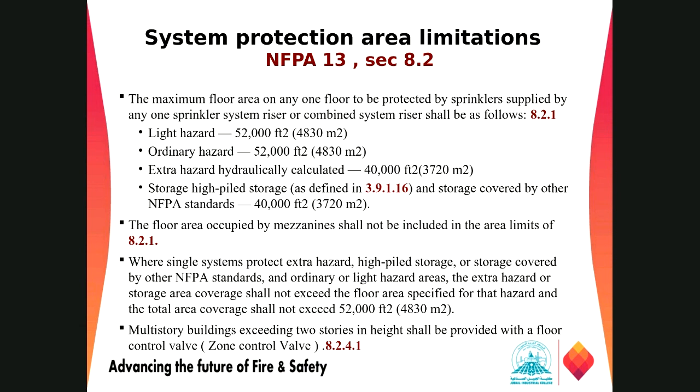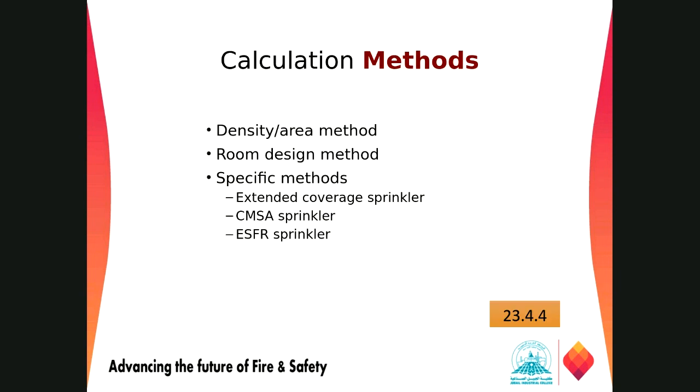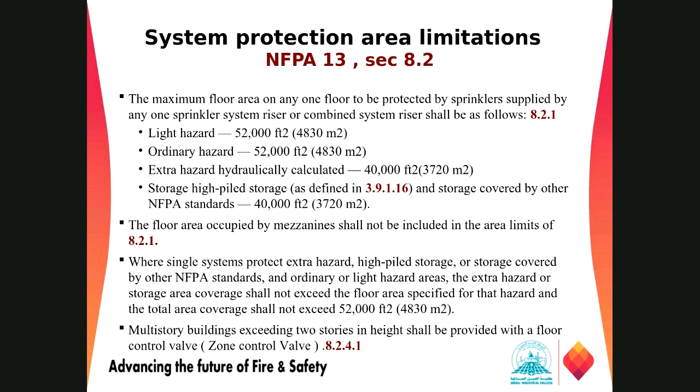Okay, moving on to the next one. System protection area limitation, I think we discussed that in the beginning, the maximum number of areas and all, right? Now here we have one requirement. If we have multi-story buildings exceeding 2 stories in height, they shall be provided with a floor control valve, or you can say zone control valve, as per NFPA 13.